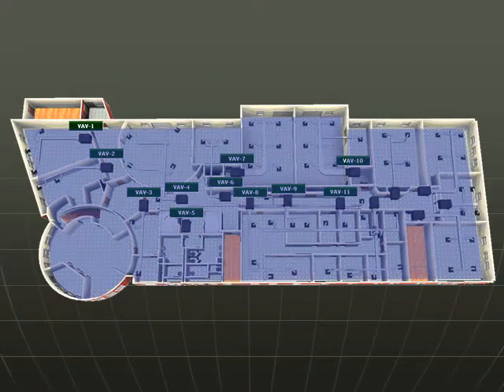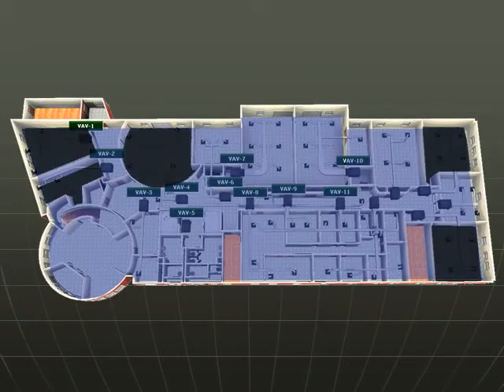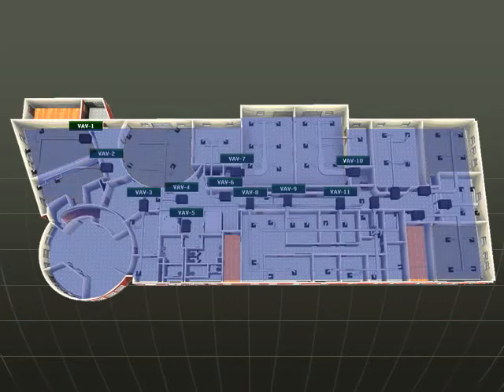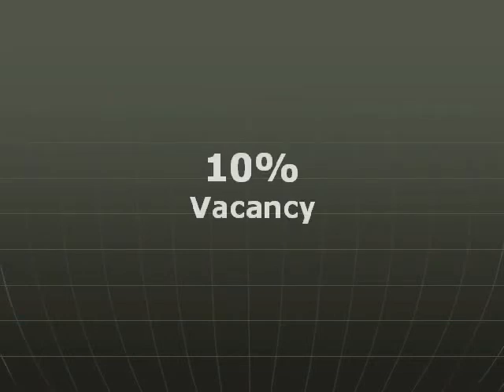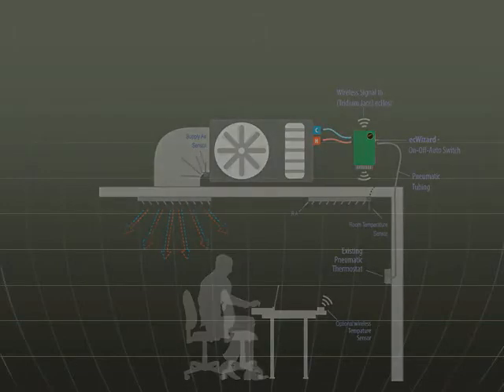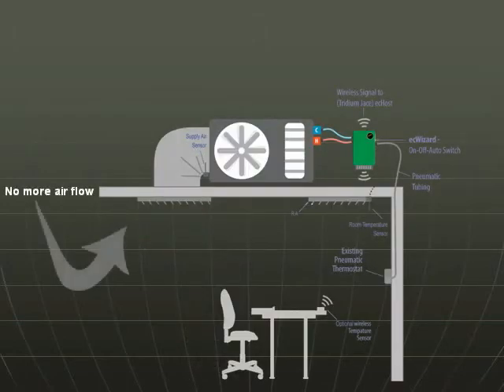The ecWizard schedules in these areas can be programmed to allow air conditioning and heating only prior to and during occupancy. If you seldom use the room or do not want to follow a scheduled regimen, then you simply have to push the sensor override button, or make an adjustment in the software to obtain air conditioning or heating for a couple of hours. Many buildings have 10 to 30% of vacant space on a daily basis. Having the ability to turn off the air in 10 to 30% of your facility each day adds up to a tremendous amount of energy savings.